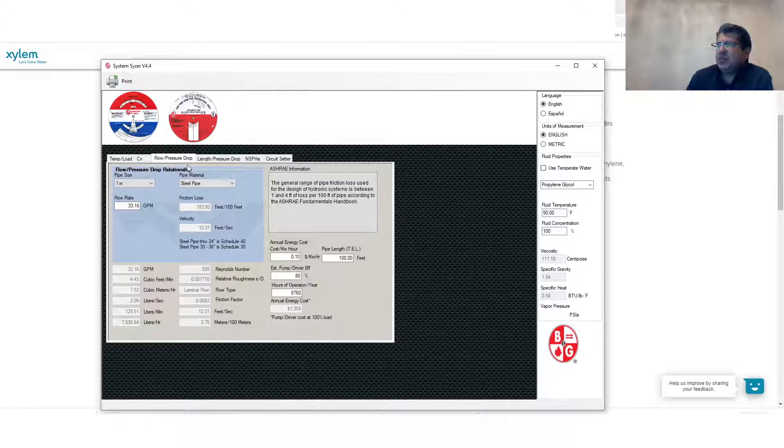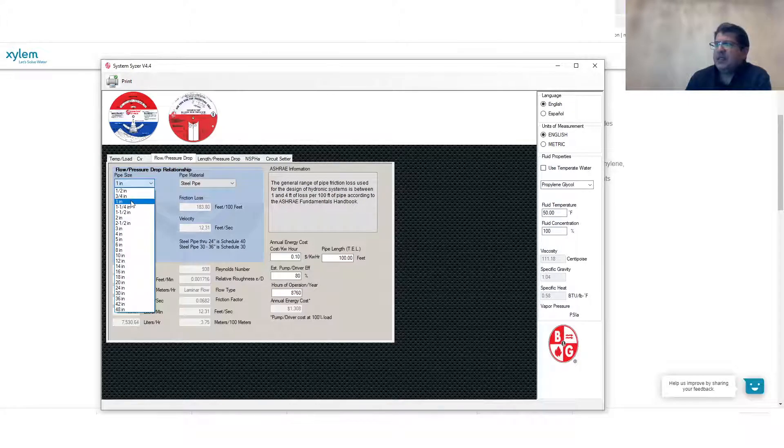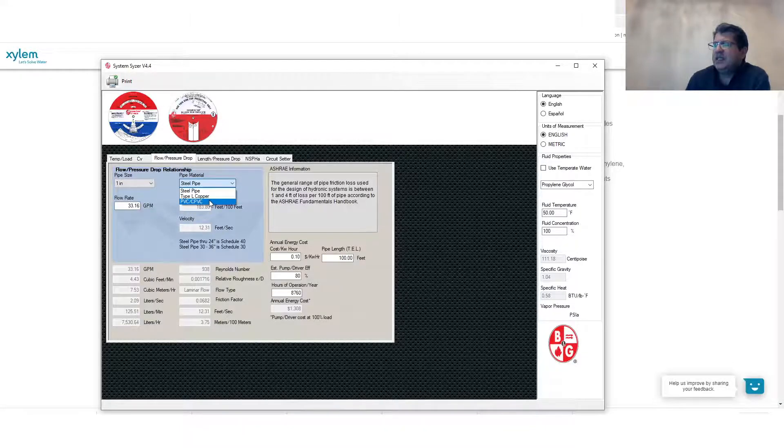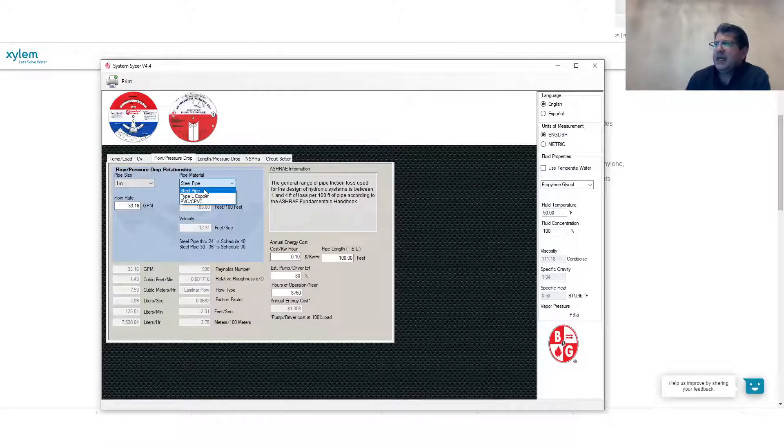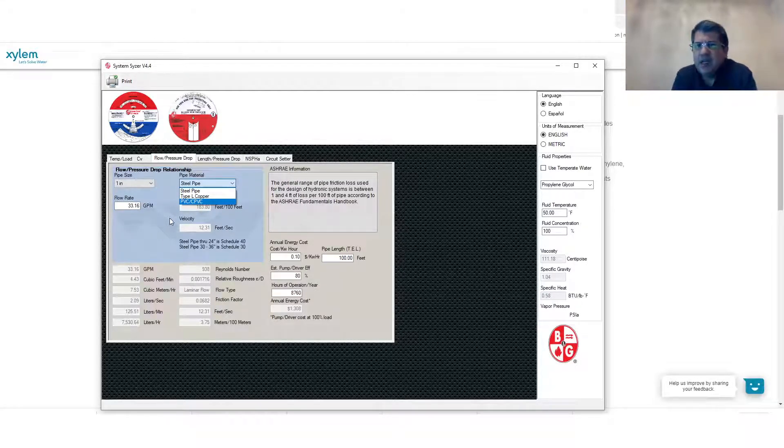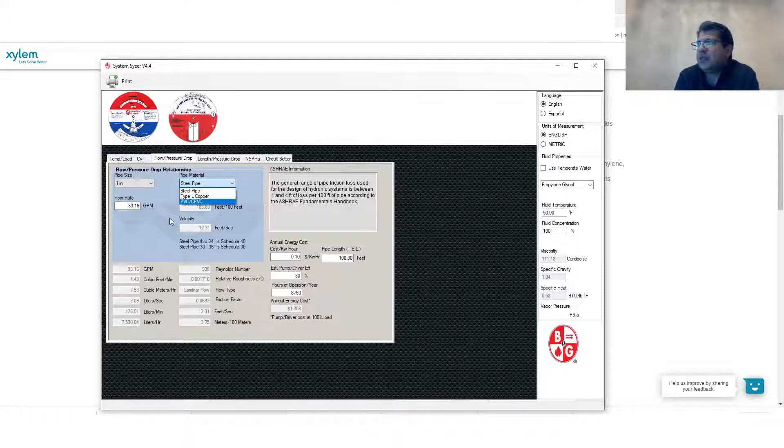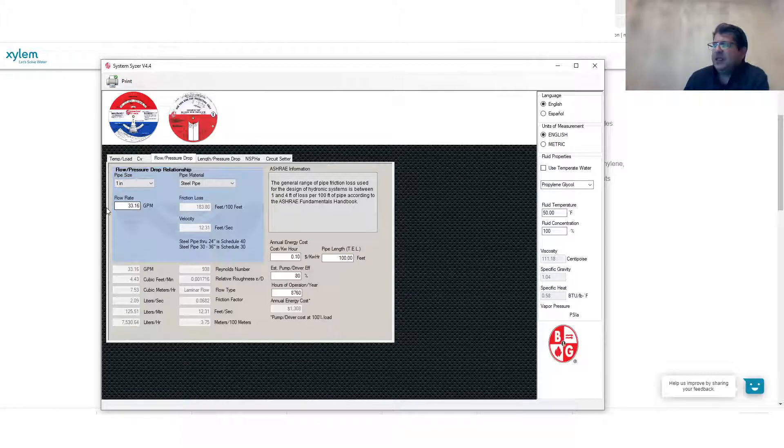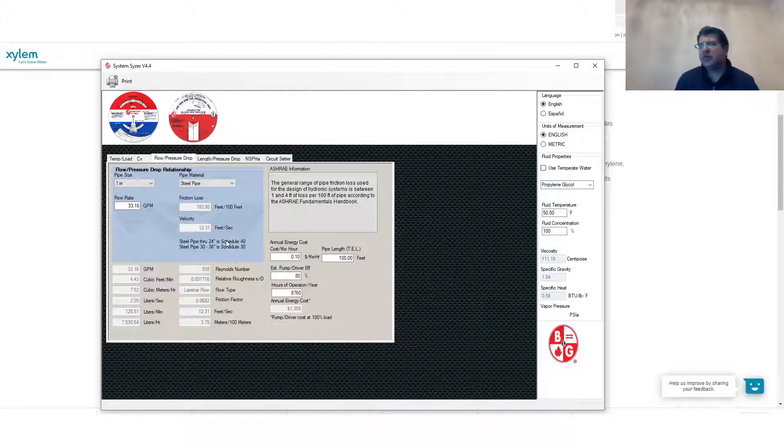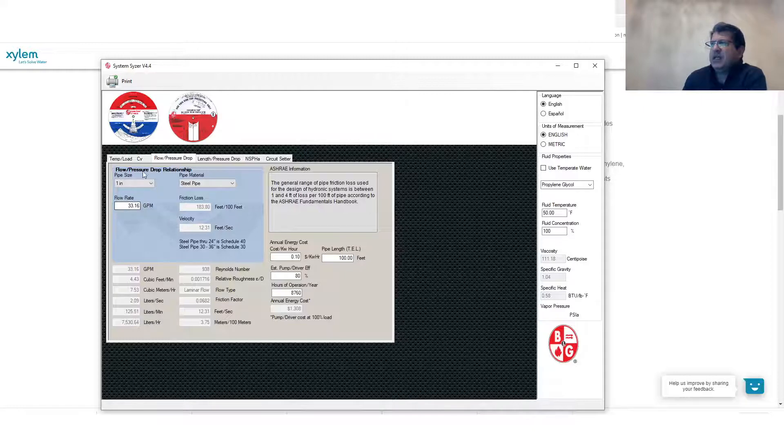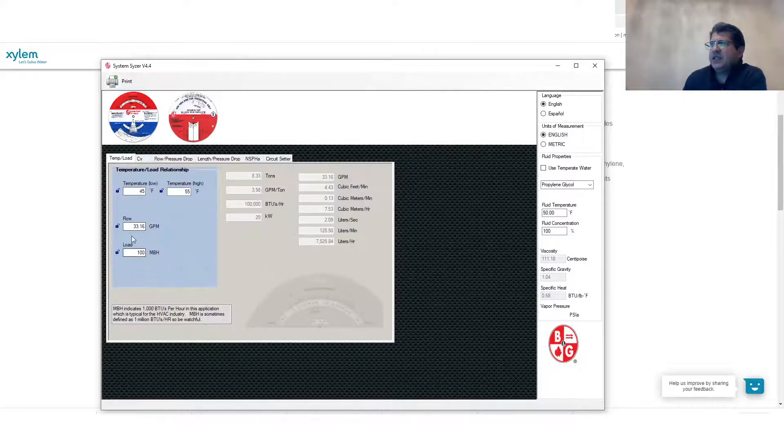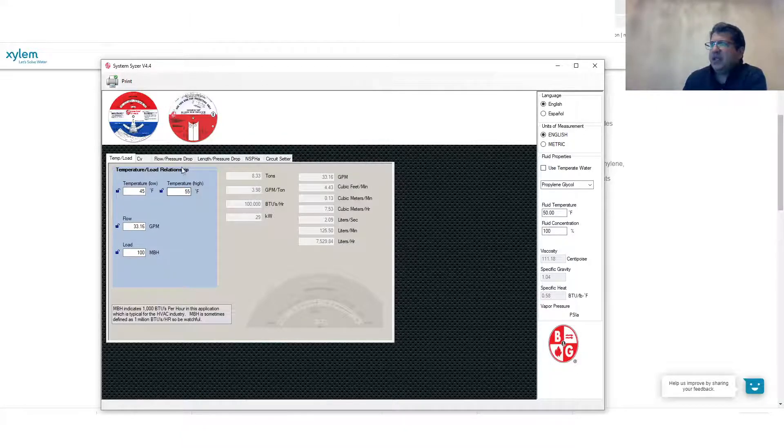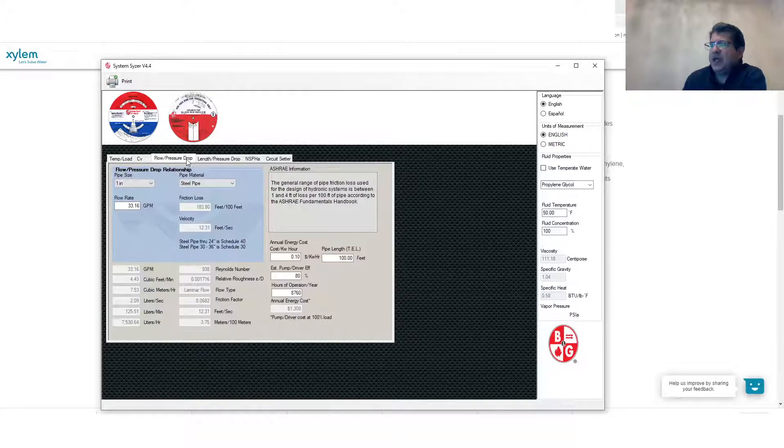As it relates to the flow and pressure drop, you can easily select the piping. As you can see, there is a different type of piping material. You have option between the steel, copper and PVC or plastic form or composite type of pipe. As you know, if you change any of this, the friction characteristic of the interior of the pipe changes and that will impact the pressure drop across your pipe. So you can select different pipe size and different flow rate and then you get what is your velocity across the pipe and also what is the friction loss that you will experience. For example, if we selected 33 in the previous tab as a GPM to offset 100 MBH and if I come to this new flow pressure drop tab, that's automatically imported in here.